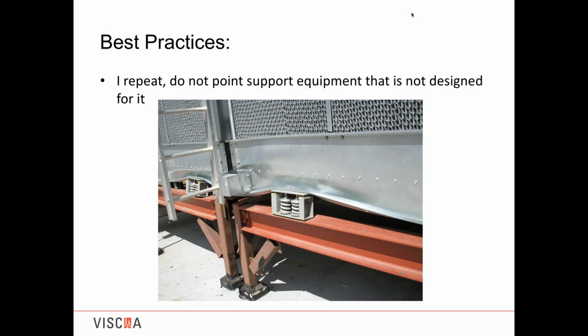So in this case, that equipment required a structural frame underneath it to distribute the load coming in at the point. By the point, I mean where the vibration isolation system is, in this case a two-spring housing. If you look at this picture, another engineer did a great job designing a well-designed frame underneath, with diagonal bracing, but it was ruined when the equipment was not properly supported underneath and somebody went with the point support.